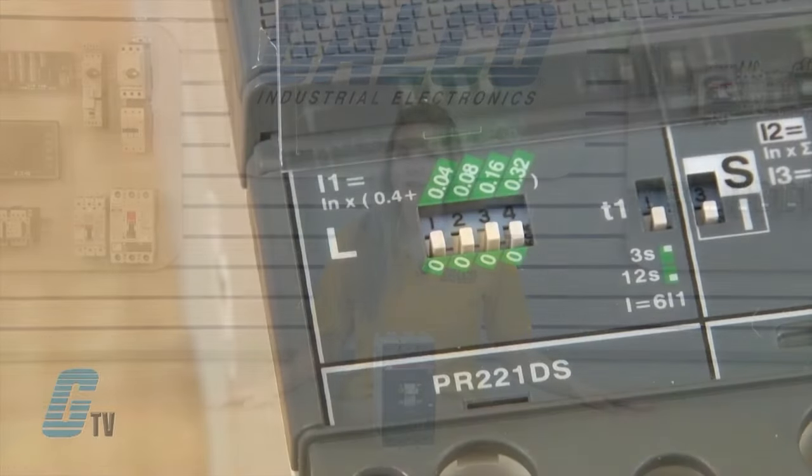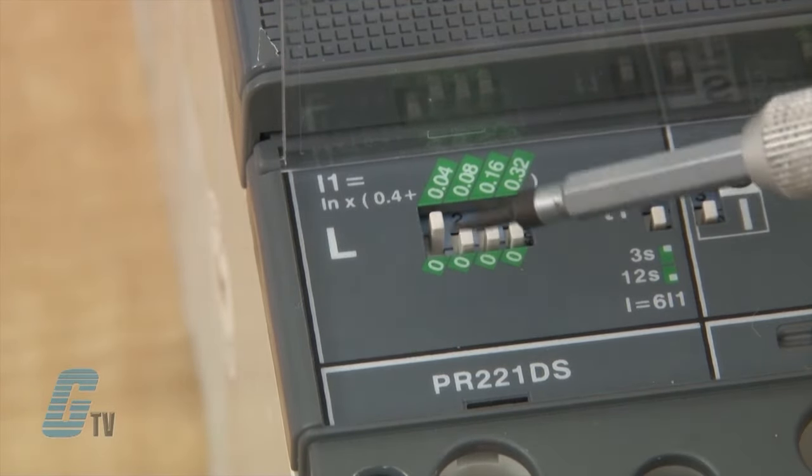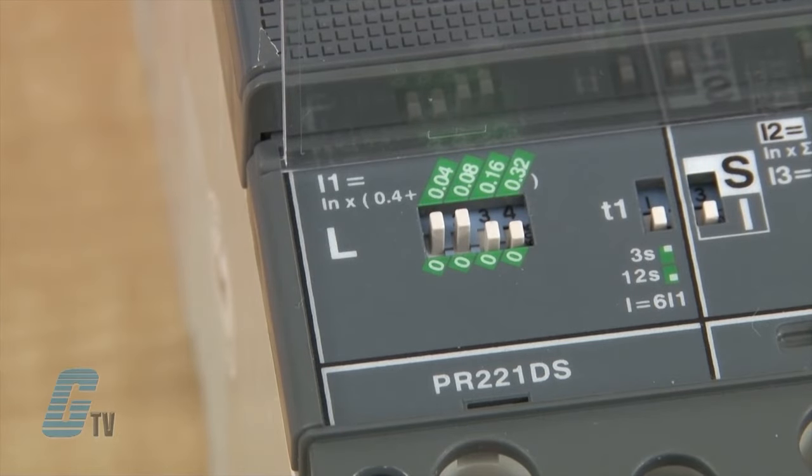The values increase in addition to the 0.4, so if I have the first two switches of 0.04 and 0.08 up, then my overload threshold would be 0.52 or 52 percent of the maximum current rating.